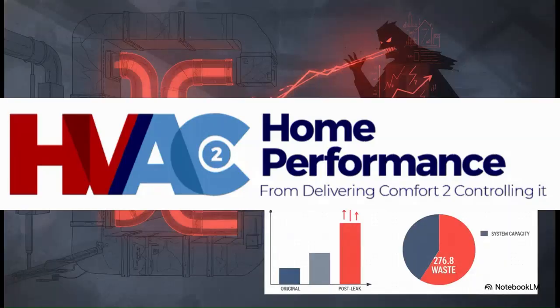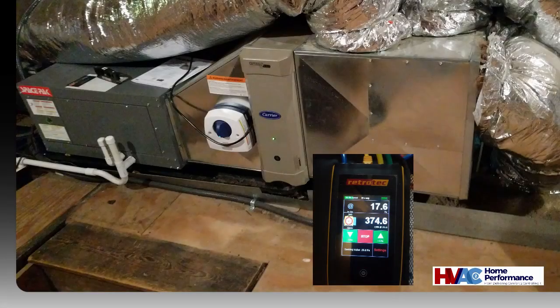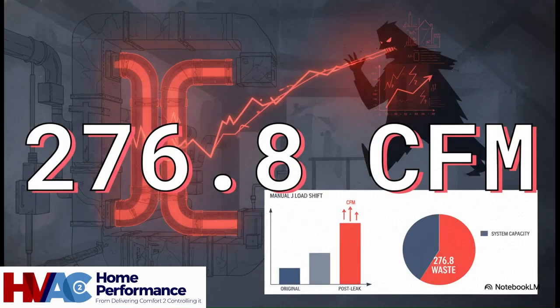So how much was leaking? The duct test uncovered another shocking number. The total leakage for that second floor system was almost 375 CFM. And of that, a staggering 276.8 CFM of perfectly conditioned air was being dumped directly into the vented, unconditioned attic. That's not a leak, that is a fire hose of wasted energy and stolen capacity, directly sabotaging that second floor system.